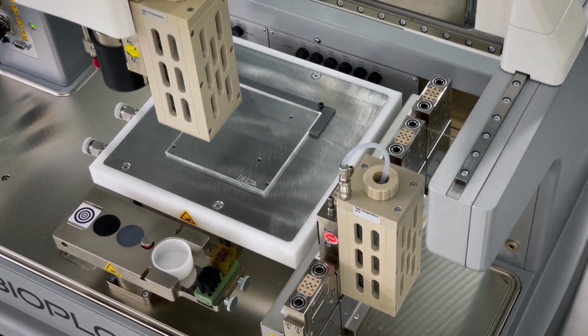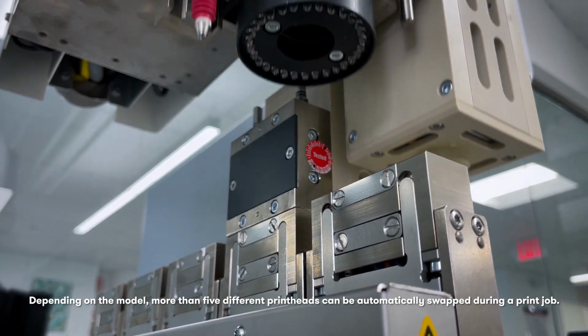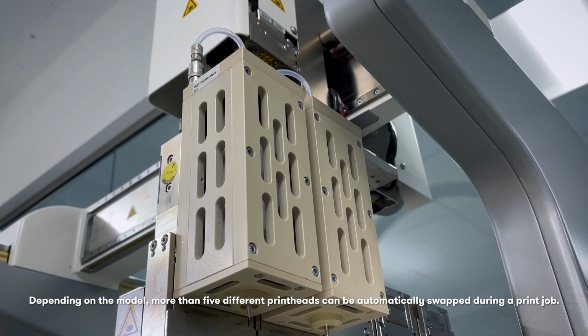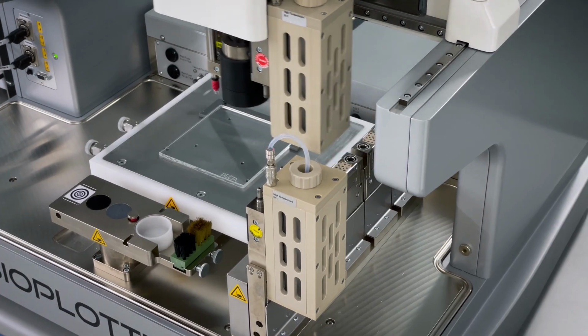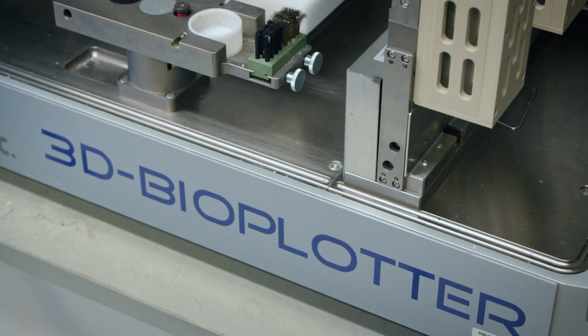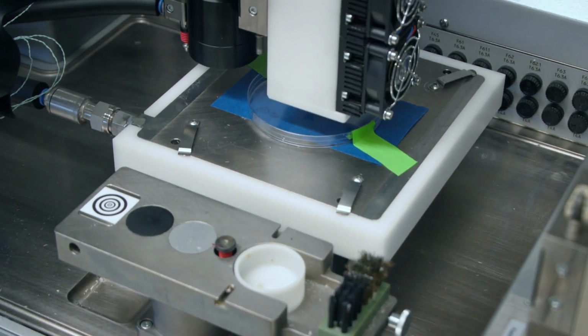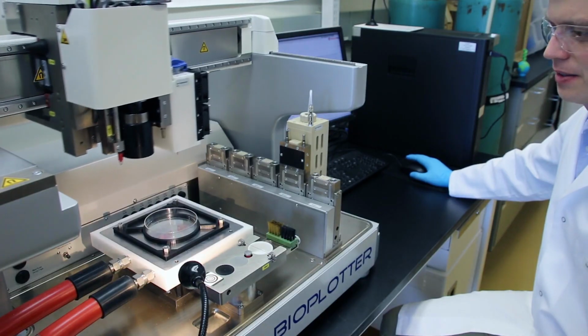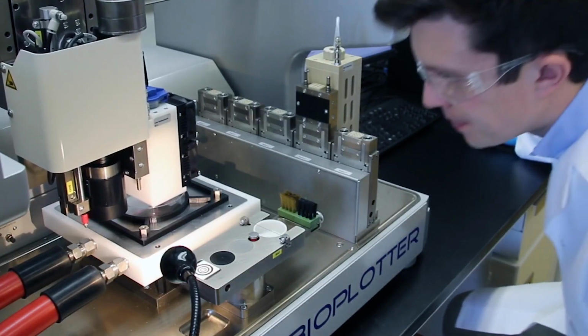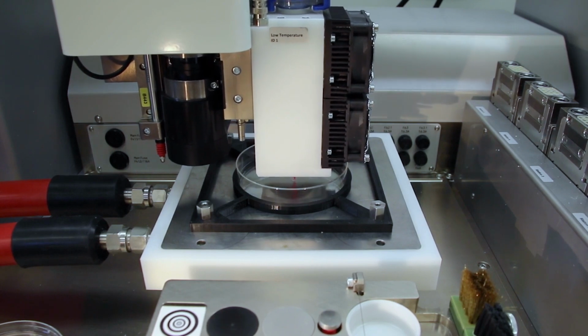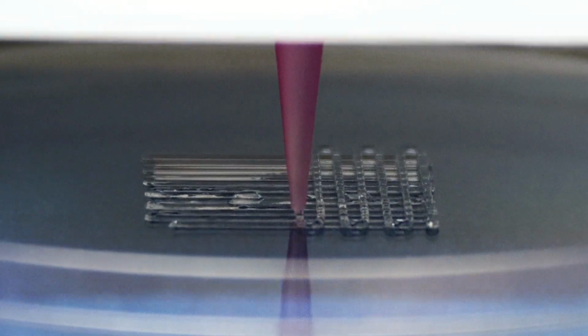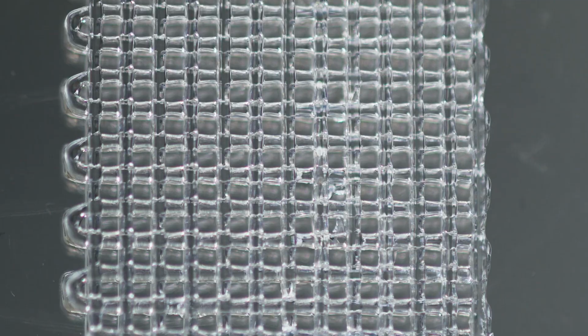The 3D-Bioplotter is a very unique solution because it has 5 different print heads that can swap in and out, including those for UV curing, for low temperature materials, and for high temperature materials that can even go up to as high as 500 degrees Celsius, which is the largest temperature range on the market. Additionally, the 3D-Bioplotter has a temperature-controlled print bed where you can bring your prints anywhere from -10 degrees Celsius up to 80 degrees Celsius as you're printing.